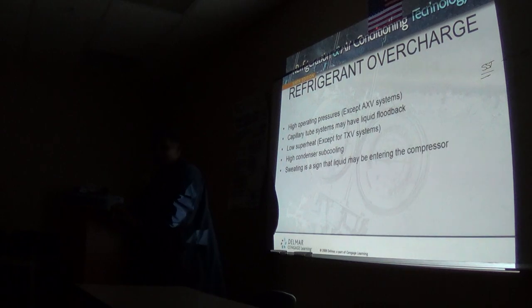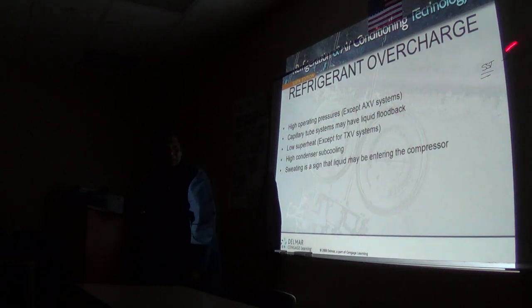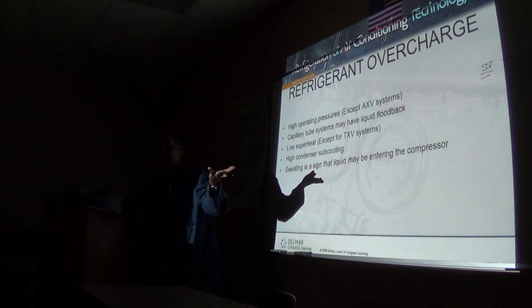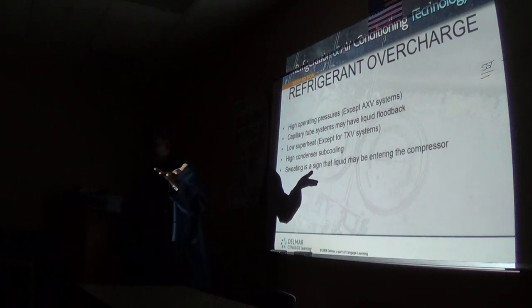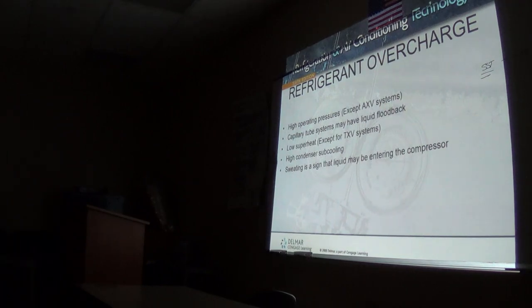Mostly on the show. Not unless they tell you, oh, there was a guy here yesterday. Now, it's pretty easy. Remember I was telling you guys that we only charge relative to the high side pressure and or condenser saturation? There is a reason, and there's a reason why you need to learn to use your gauges.